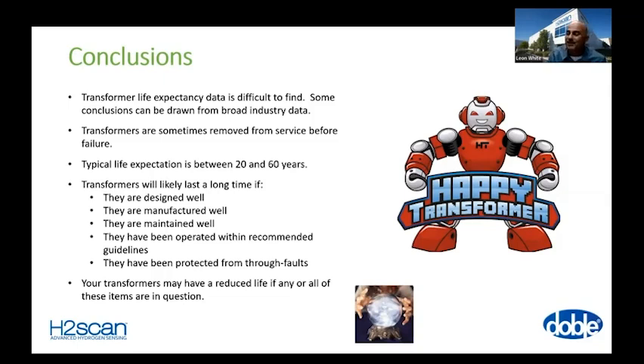So in general, depending on the criticality of the transformer, you're going to install monitoring appropriate for the criticality of the asset. Most of the time the value of the transformer is very small compared to the process or the revenue at stake if you lose that transformer. And so most utilities' large transformers are installed with redundant systems so that if one fails, others in the system can pick up the load. But as you move farther down to the distribution level and so forth, that may or may not be the case. So again, what's monitored and the alarm set points: if you're looking at a hydrogen monitor, or bushing monitoring or partial discharge monitoring, that's where you look at the standards and you look at the suppliers of the monitoring equipment for recommendations on those alarm points.